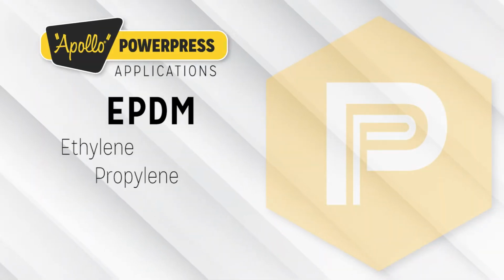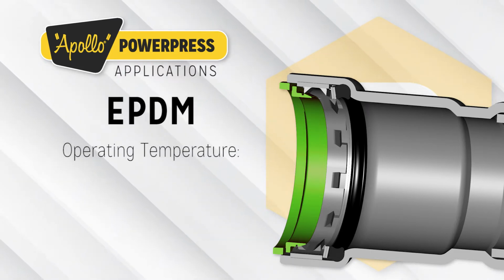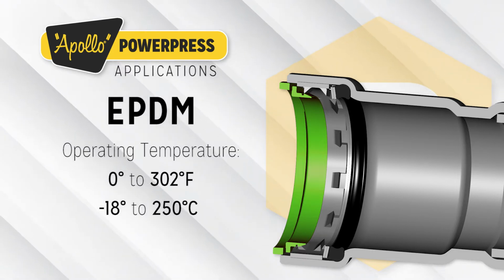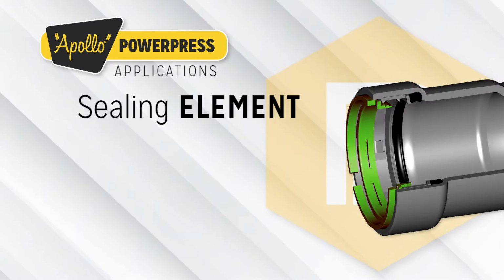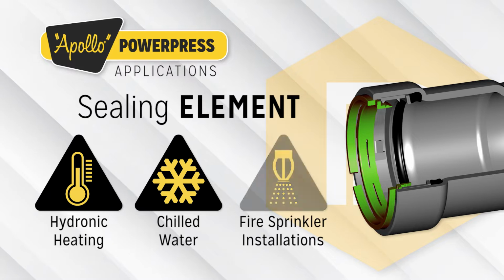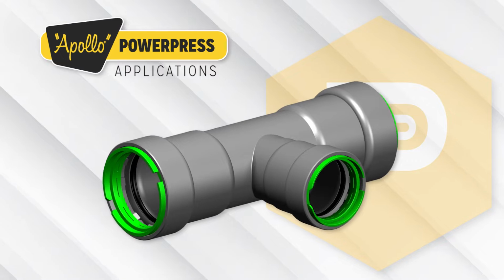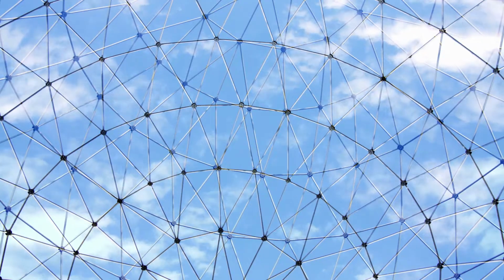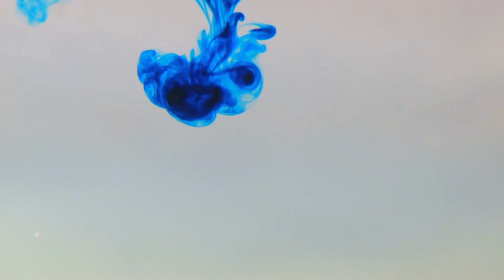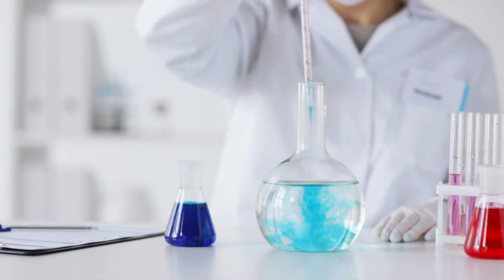EPDM, or ethylene propylene diene monomer, is shiny black in color and has an operating temperature of 0 degrees to 302 degrees Fahrenheit, negative 18 degrees to 250 degrees Celsius. This sealing element is used mainly in the applications of hydronic heating, chilled water, and fire sprinkler installations. The EPDM sealing element possesses excellent resistance to aging, ozone, sunlight, weathering, environmental influences, alkalis, and most alkaline solutions and chemicals used in a broad range of applications.